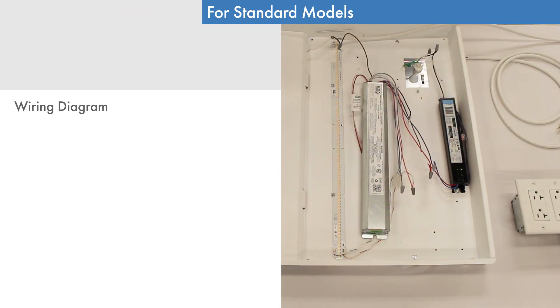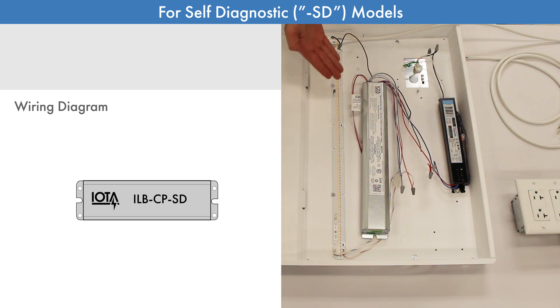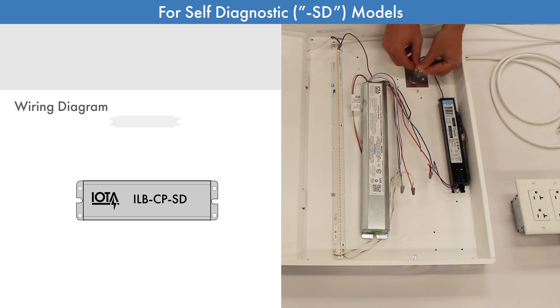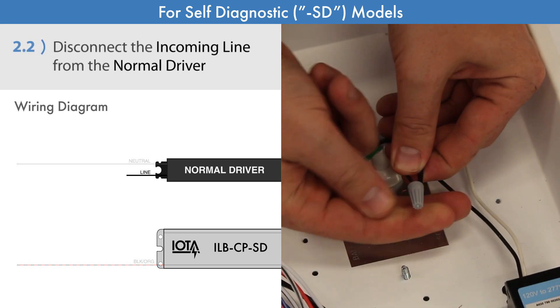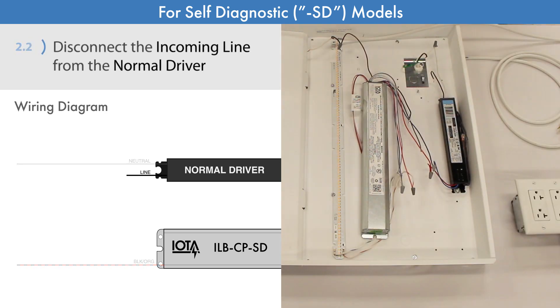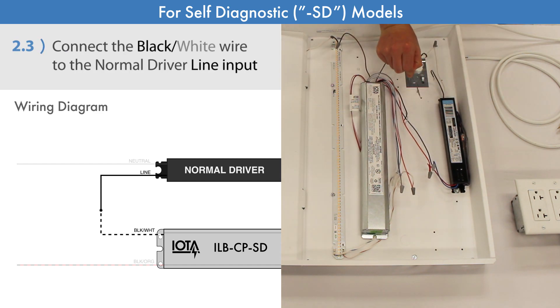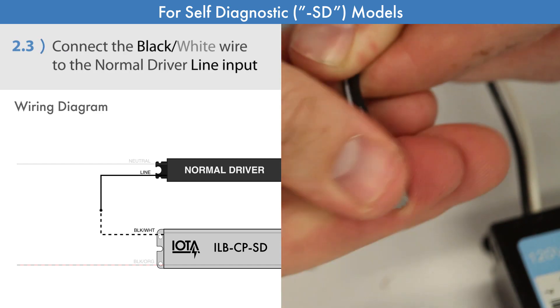Now let's switch to the wiring for the ILB-CP SD self-diagnostic units. Unlike standard ILB-CP models, the incoming neutral wire should remain connected to the normal driver, and instead we will disconnect the AC line input from the normal driver. Then, we will connect the black-white wire to this normal driver's AC line input.